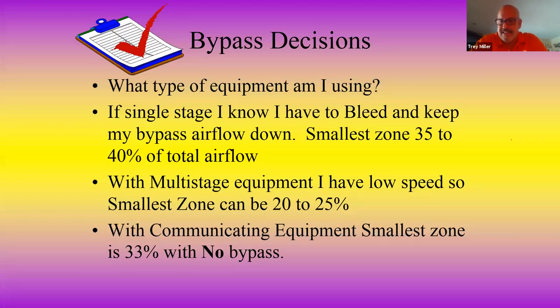But then again, guys, to me, the best value is your two-stage equipment with a smart bypass damper, and you've got one heck of an efficient system. But we do make the boards, and we make the dampers for a lot of the communicating systems, and installed properly, they work very good also.